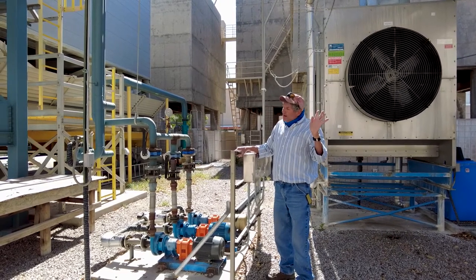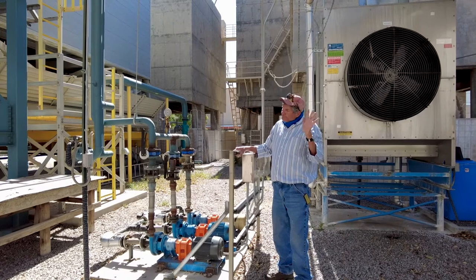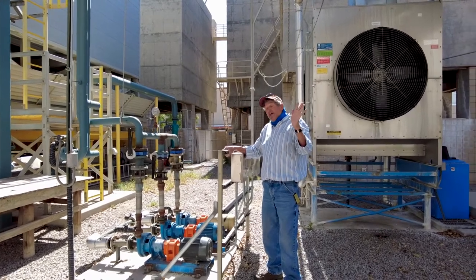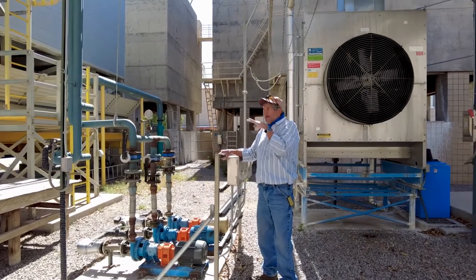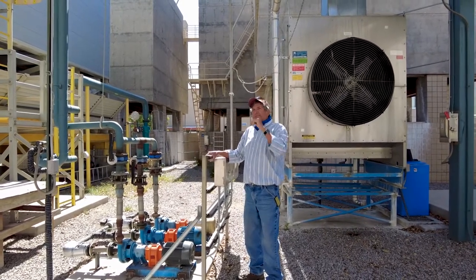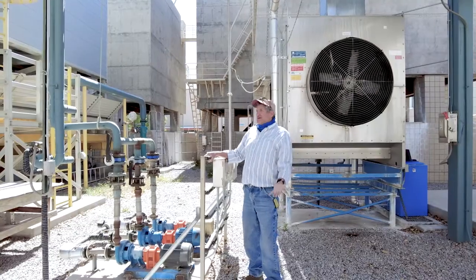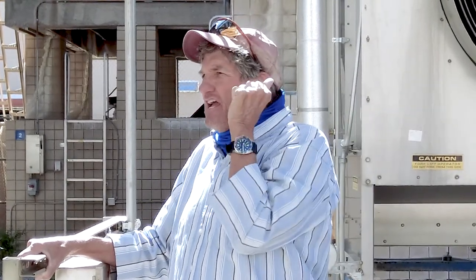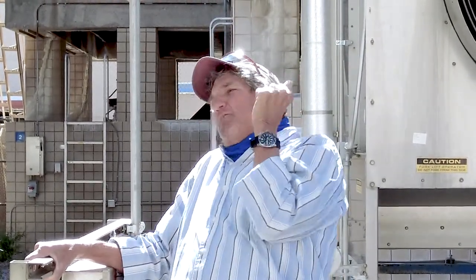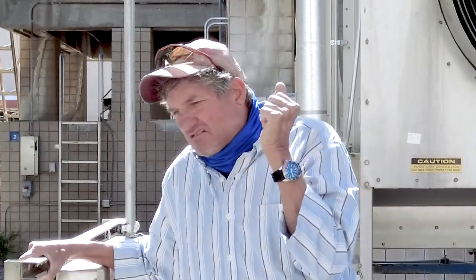We usually don't have problems with the turbine, except that day. We switched everything over, had everything working. That was about 8 o'clock in the morning. We started about 6, got everything back on track by 8. Working perfectly. 10 o'clock, I get a call from the electrical engineering department over here. Satish Ronaday says, hey, Dale, we're getting a single phase condition in the building. What the hell's going on?